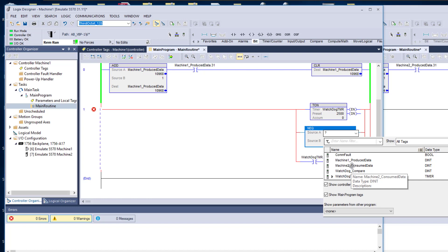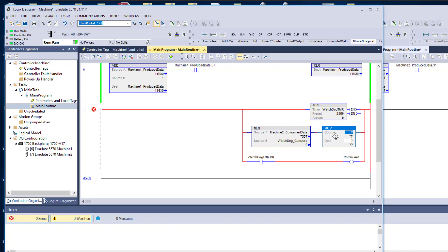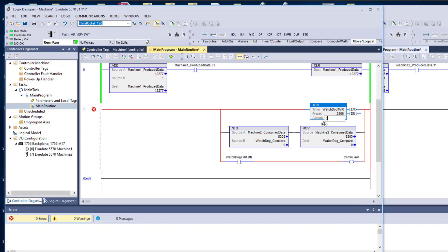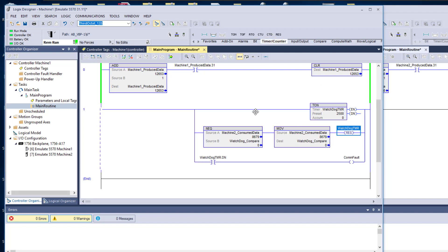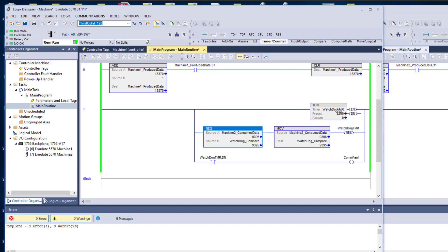We're going to load this — move this into here. As we move that into there, we're going to say if the data is not equal, we're going to load it in there. Put that at zero. Then what we're going to do is a reset — in timer, we're going to reset this timer right here. So what we're saying is: if the data stops talking and you compare it against itself, if it's not equal to, it's going to move itself into that. If it stops for any reason, this timer won't reset — it will automatically start timing. Once it hits two and a half seconds, it will fault out.